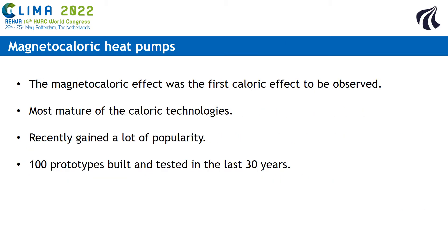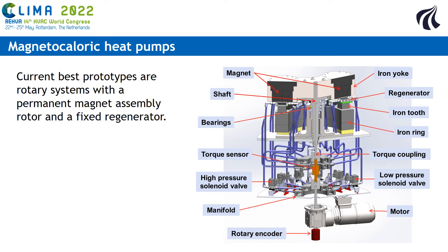The magnetocaloric effect was the first caloric effect to be observed, and that's why it's the most mature of the caloric technologies. It has recently gained a lot of popularity within the scientific community. In 30 years, there had been around 100 prototypes built and tested. The design of the current best prototypes for magnetocaloric heat pumps are rotary systems with fixed regenerators and a rotating magnet assembly. You can see on the right a schematic of a typical magnetocaloric heat pump with the rotating magnet assembly on top, the regenerators below, and under the pipe and valve system.